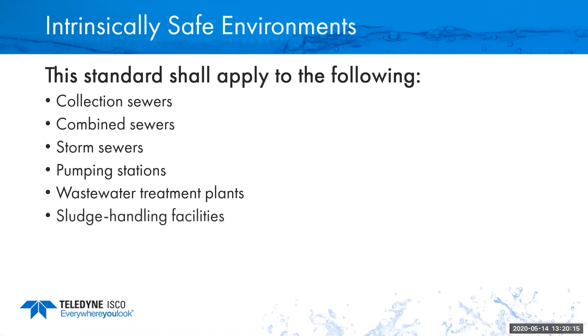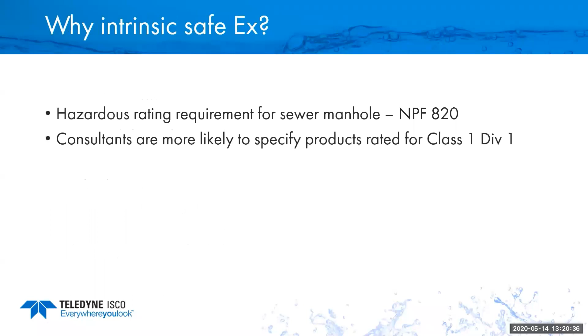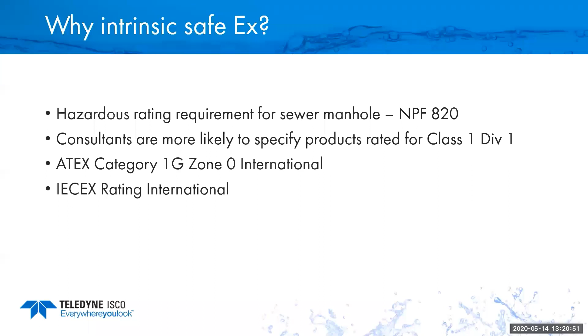So the hazardous rating for a sewer manhole is typically rated Class 1, Division 1, and more consultants coming out of college especially are specifying Class 1, Division 1. And why not? If the capability is there, you're just adding another layer of safety. In Europe, they use what's called ATEX Category 1G, or Zone 0 for international. And there's also different ratings, the IECEx rating, for other parts of the world.